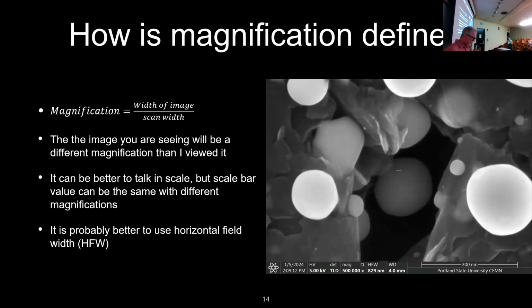The next thing people tend to talk about are scale bars, but the problem with scale bars on most microscopes is that the scale bar will change with magnification and length before it jumps to the next size range. In this case, where we have a 300 nanometer scale bar at 500,000 magnification, there's a range of magnifications that would give me a 300 nanometer scale bar. Saying a 300 nanometer scale bar doesn't always mean a whole lot to me. Horizontal field width is a great one. You'll see that in the middle of the data bar at the bottom. Horizontal field width tells us the width. In this case, it's about, let's call that, 7/8 of a micron. It's a little bit less than that. That's getting there pretty good.